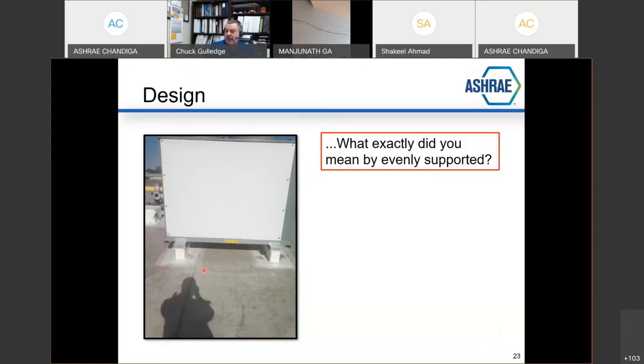The roof got repaired, flashed in, the equipment got lifted up in the air and set down, and people were standing around going, well, why does it look that way? Somebody looked at static drawings, the way the drawings got plotted, there was like a break line in the drawings right here. That base was on one drawing, this base was on another drawing. Somebody measured those drawings wrong and set one of these in the wrong location, and nobody checked it, and nobody checked this when it was on the ground to make sure that centerline spacing was going to work.